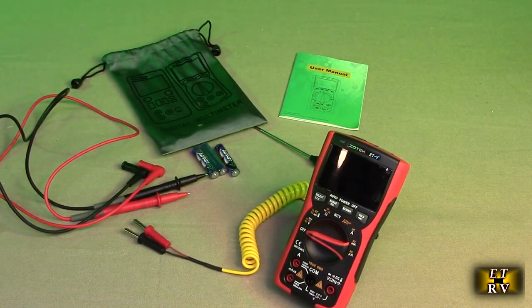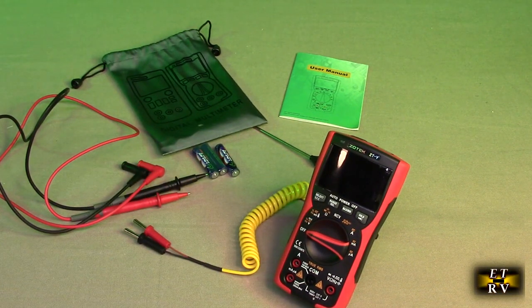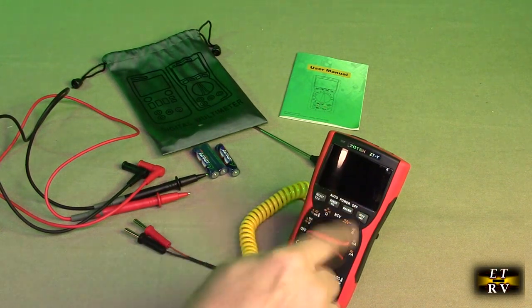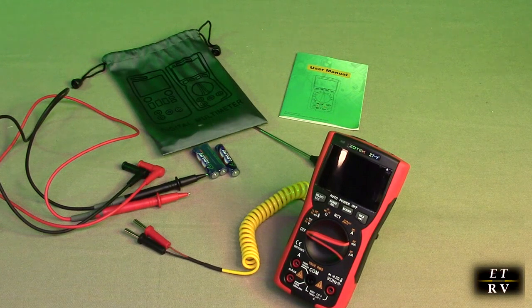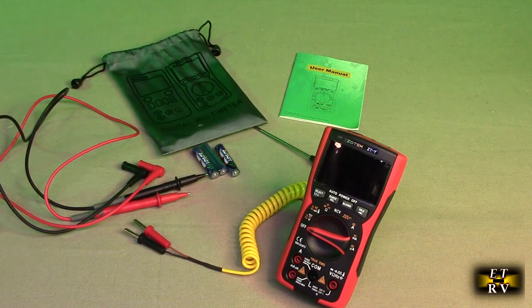This is about 59 by 38 millimeters LCD screen, so it's nice and large. It has an analog bar, and it'll dim itself down after 15 minutes of no activity to help save those AAA batteries. It has an anti-break design, which makes it pretty durable if you were to drop it - it's been tested for a 2-meter distance drop. It also has sealed ports so dust won't affect it. It complies with category 3 1000 volt and category 4 600 volt safety levels, and has internal fusing inside, so if you were to overdo the current, there are fuses you could remove and replace inside the unit.